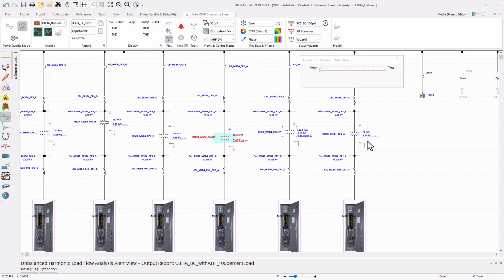So when a transformer is subjected to a load current having significant harmonic content, additional eddy current losses in the winding and also in the metal parts of the transformer elevate the temperature of those parts above their normal operating temperature, leading to the loss of life expectancy of the transformer. And to avoid such scenarios, ETAP calculates the derating factor for load currents and flags derating alerts for both primary and secondary windings of the transformer. So let's take a look at the alert view in this case.